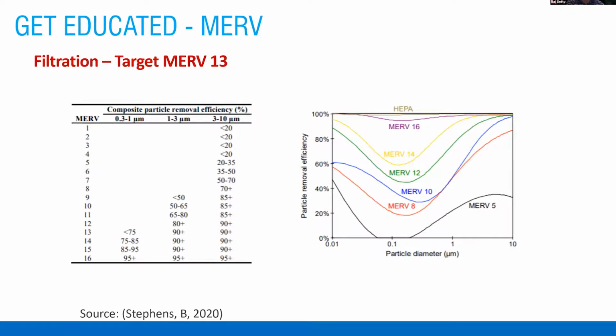And then you can see the table on the left is about the efficiency and where you're trying to target. There are going to be downsides to changing the filters, but new designs, as you start writing new OPRs, should have a minimum of MERV 13. And also think about the passes and air change rates. So this is where we get to that delta between MERV 13 and HEPA. Luckily, LEED has been mandating MERV 13, so many modernized buildings do have that at this point.